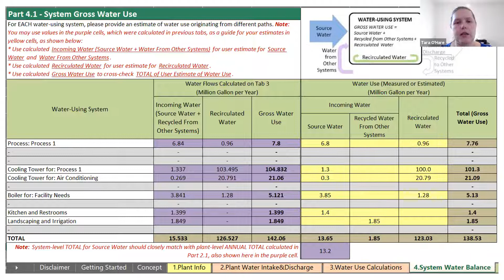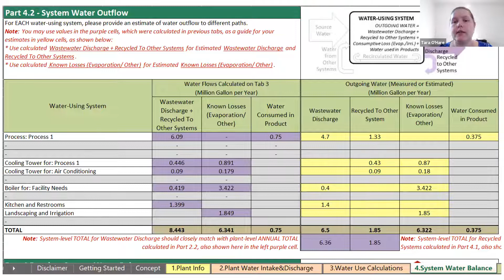They have some that you can strap onto the pipe run, called acoustic flow meters. Those can be helpful because you can move them around the system instead of permanently plumbing them in. So things like that, or water monitoring devices, can be really helpful to get this information.